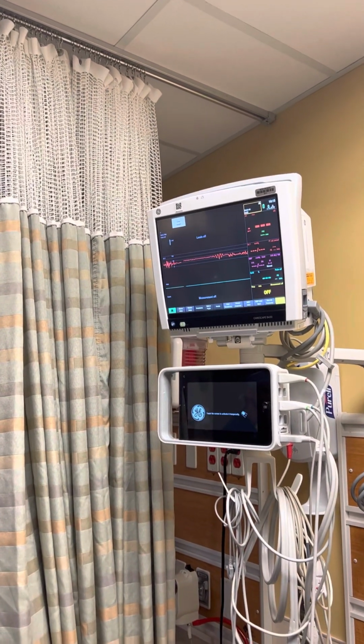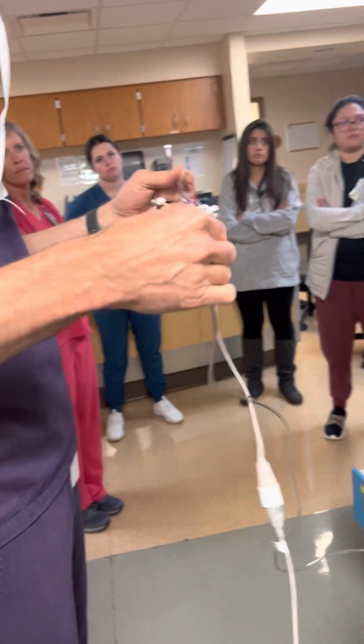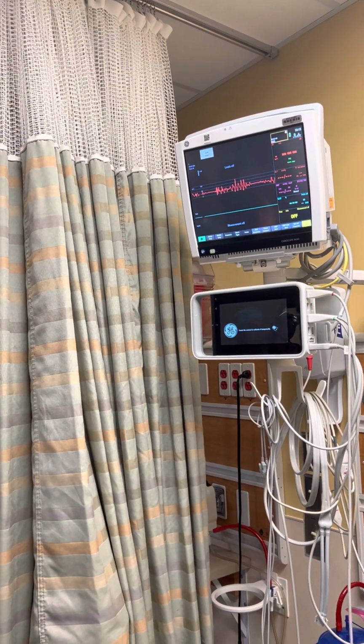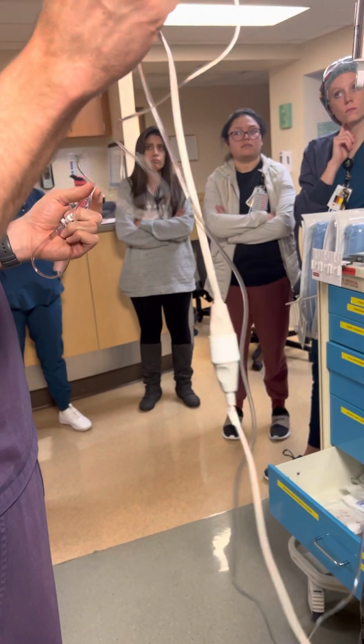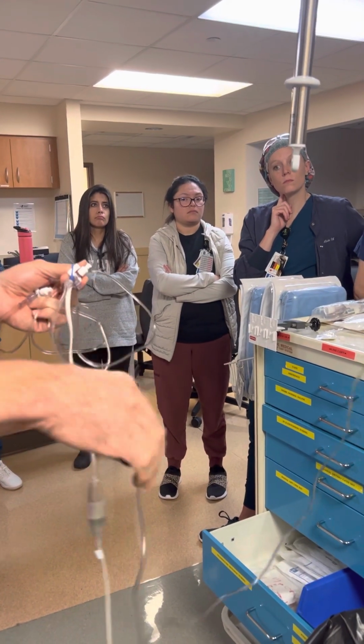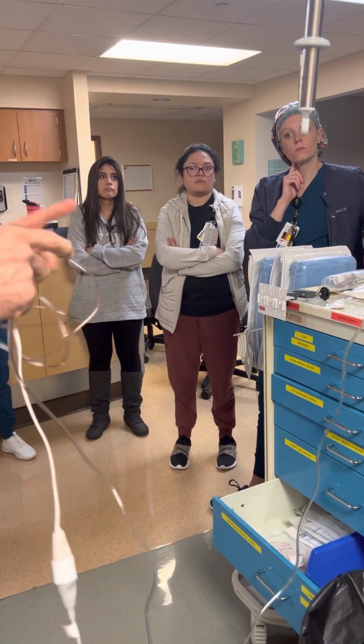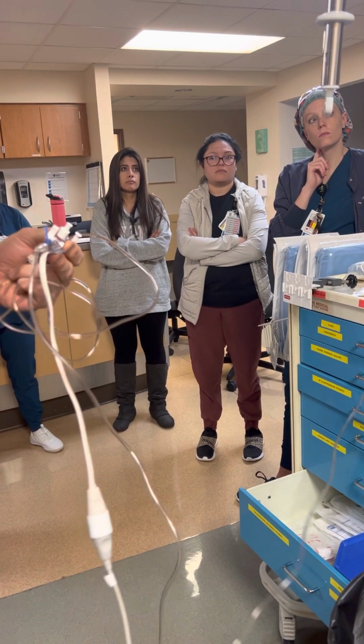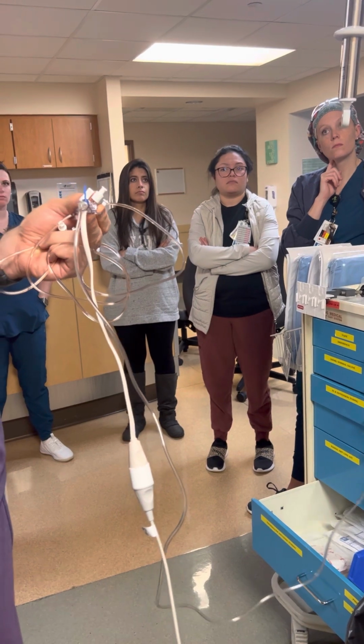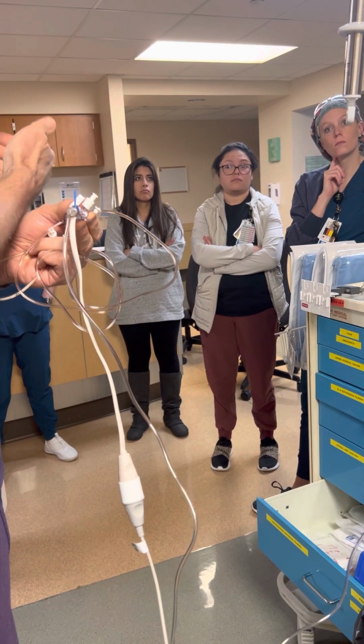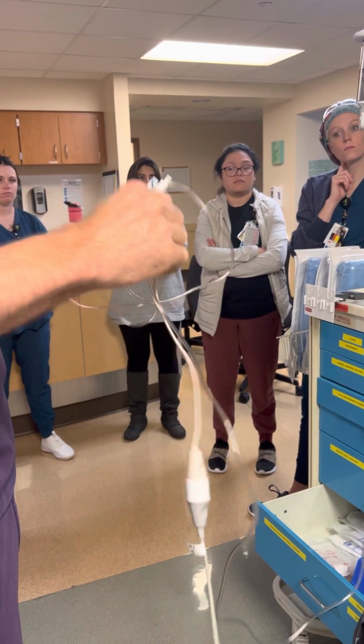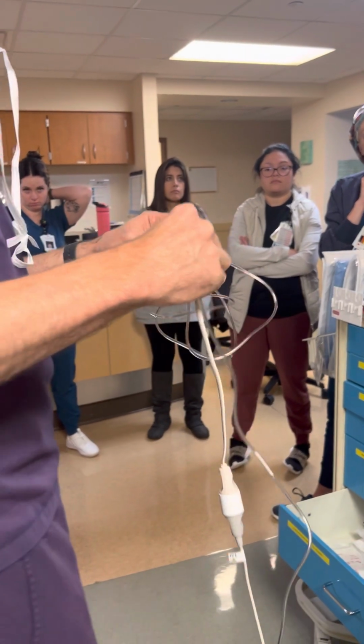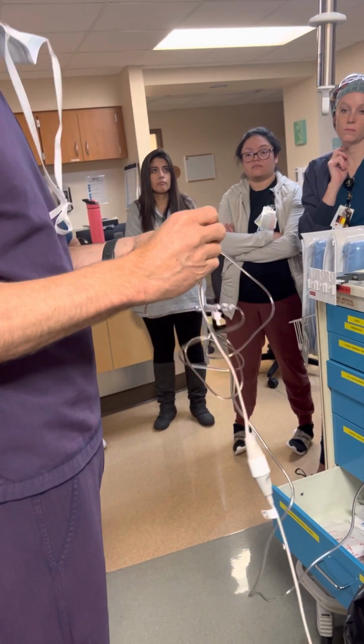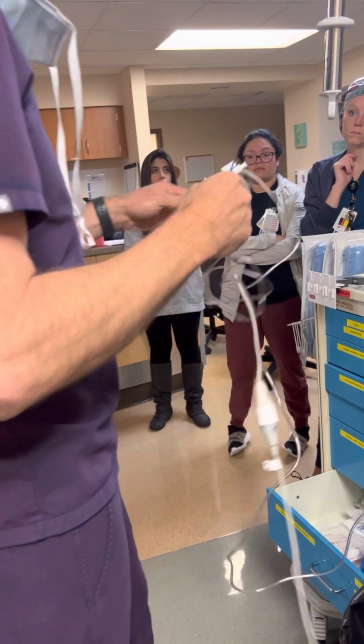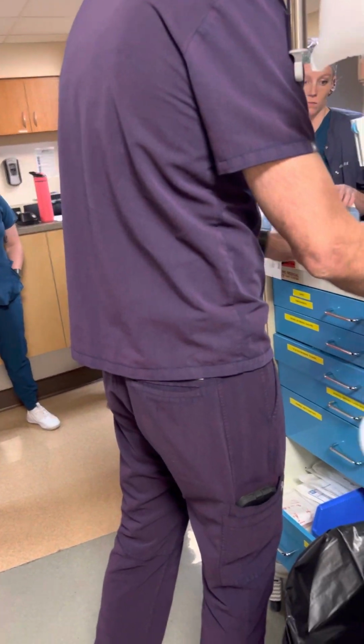So this is reading this transducer, right? There's fluid in here. So if I jiggle this fluid around, it's going to read the pressure that it feels. So it's a rough check to see if things are working. If I wiggle this and I see a tracing up there... I had the last one where I put the catheter in, but I looked on the monitor and it was a flat line. It's either that I'm not in, so the patient's not giving me a pulse. But I just went to the transducer and gave it a jiggle, so I knew that this transducer is reading pressure. That lets me know that it is measuring pressure.